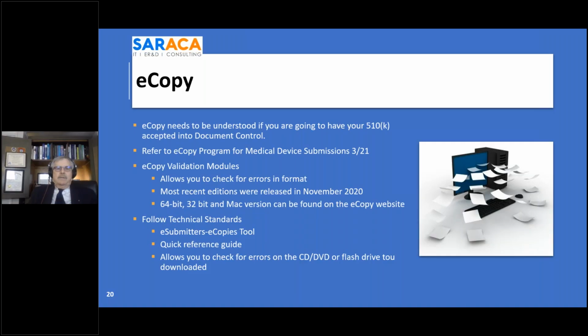And one of the most common mistakes is you don't follow the technical standards. They have to be done in a certain manner. And there are e-copy validation modules that you can download from the e-copy program that allow you to check for errors in formatting. The most recent editions were released in November 2020. There's a 64-bit, 32-bit, and Mac version that can be found on the e-copy website. It's very simple. You download these onto your computer that you're going to use to make your copy for submission. And you run it through on either your CD, DVD, or your flash drive, and it tells you whether it meets the technical standards or not.